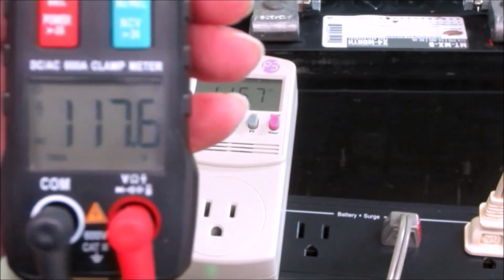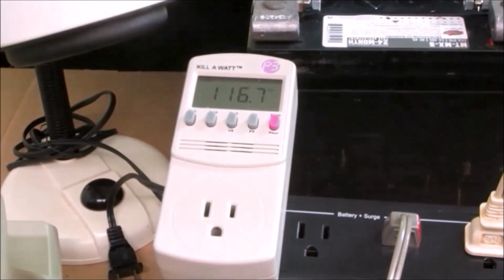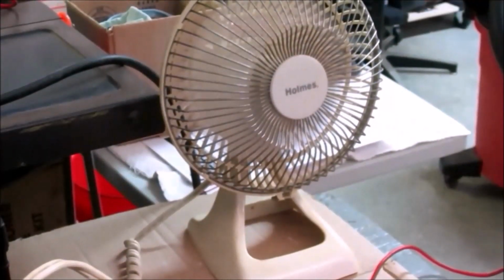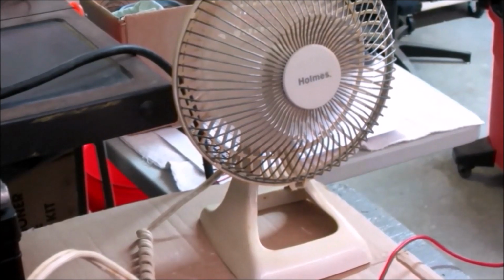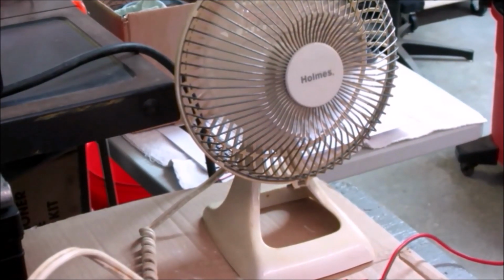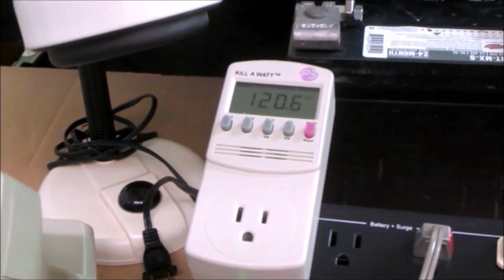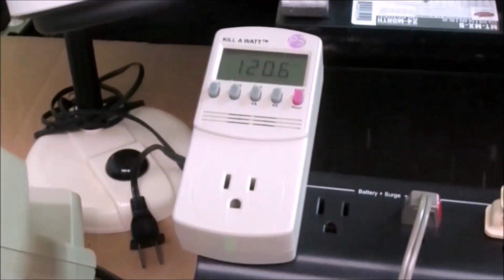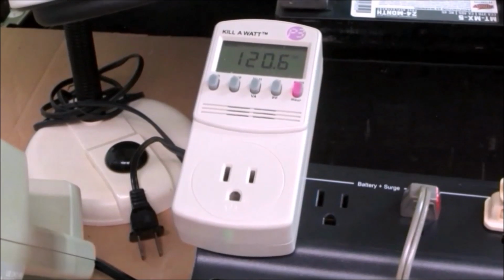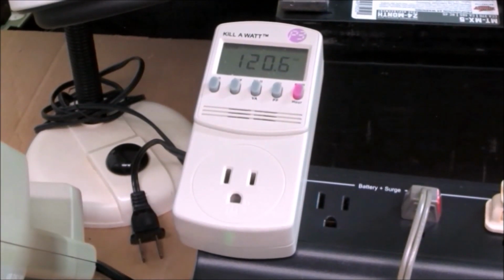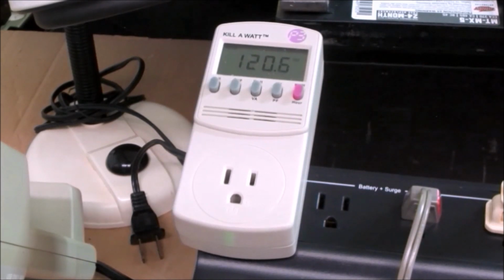So we have two meters advertised as true RMS, and they're telling me there's nothing wrong with this AC power. And yet, that fan is barely running. So what's going on here? Let me turn the AC back on. Hear the click, fan comes back up again. A difference of 3 volts is not going to cause that. That fan will run perfectly on 117 volts of clean power. So these meters, the 3 we've shown so far, highly suspicious.